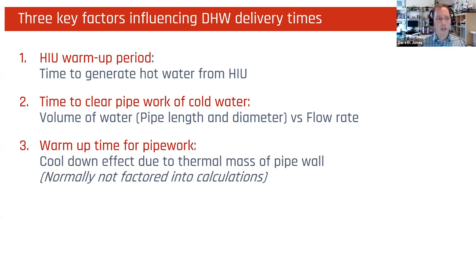There's actually a third element, which is the warm-up time for the pipework itself. So there's a cool down effect due to the thermal mass of the pipe wall. And that's not normally factored into calculations, but can actually have a really big impact. And it's quite difficult theoretically to calculate as well.